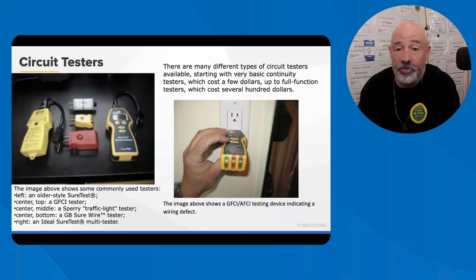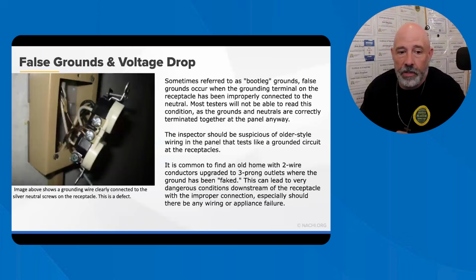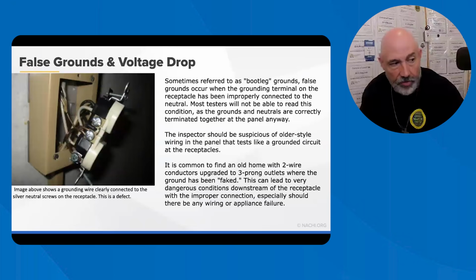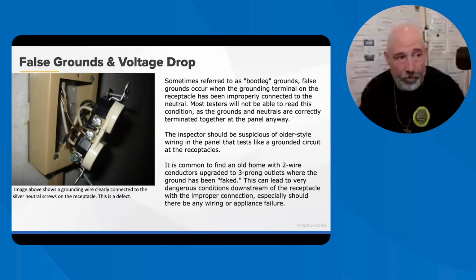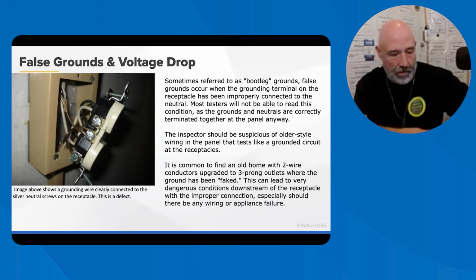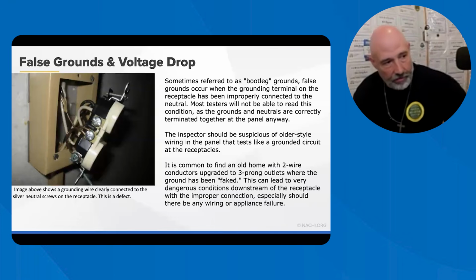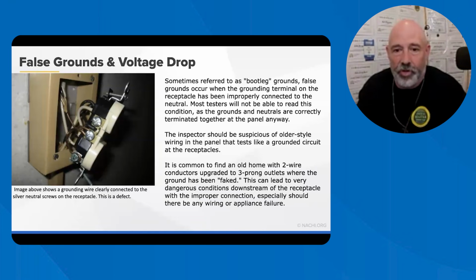I've got an AFCI tester too, and I'll sometimes pull that out if I don't check it in the electrical panel. You want to make sure of the false grounds or the voltage, you might have seen this in older houses where there is a false ground or a bootleg ground. Sorry about that, I got a phone call. Also, the voltage drop can indicate too many outlets on a service, poor connections, or undersized wiring. You want to make sure that you're pulling all this stuff out.